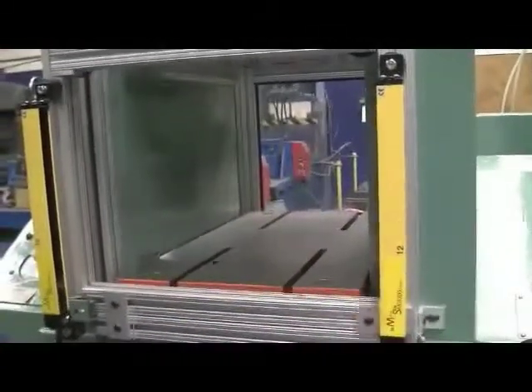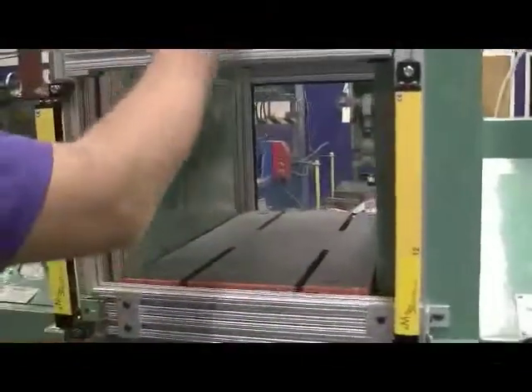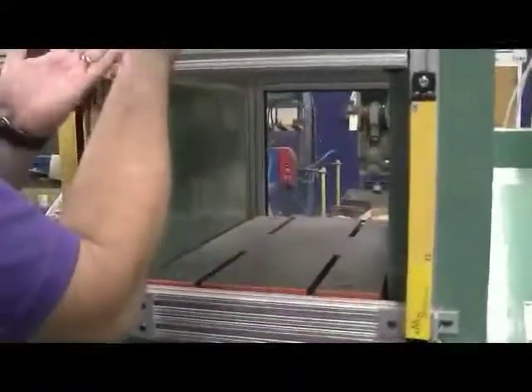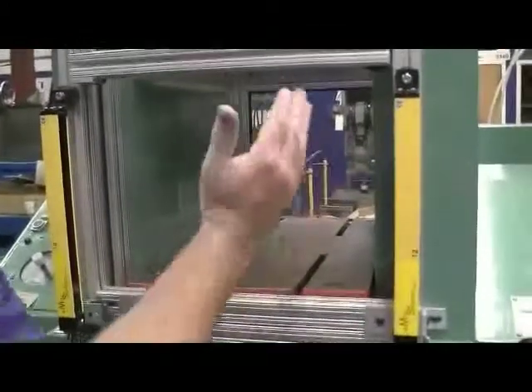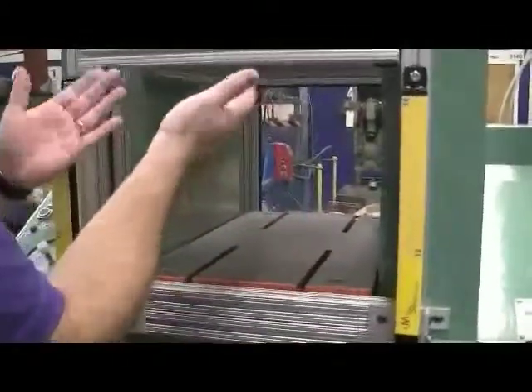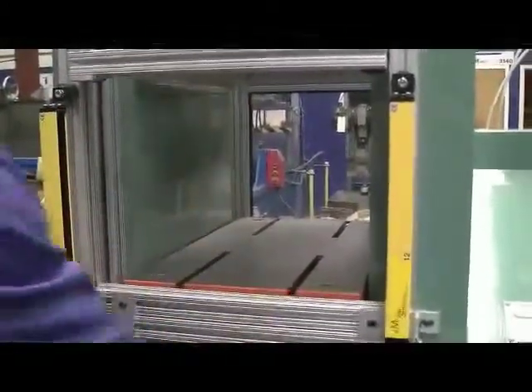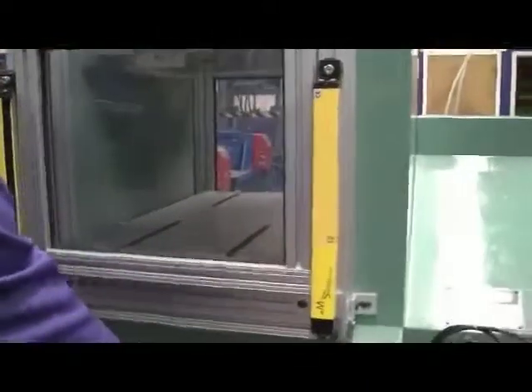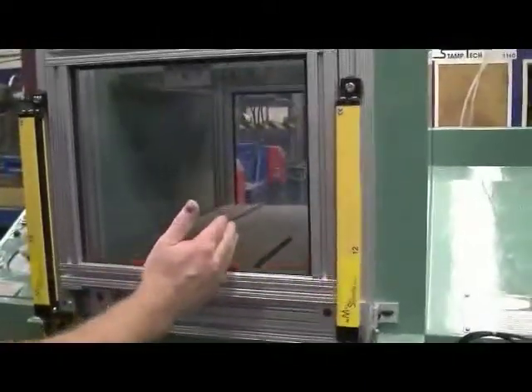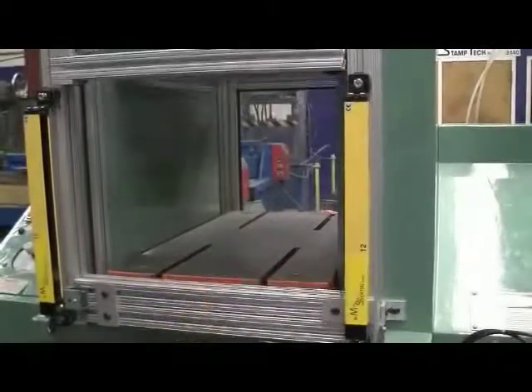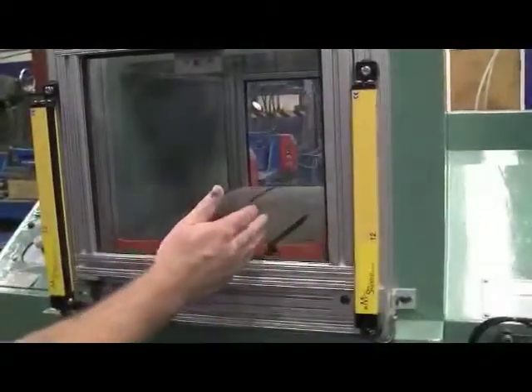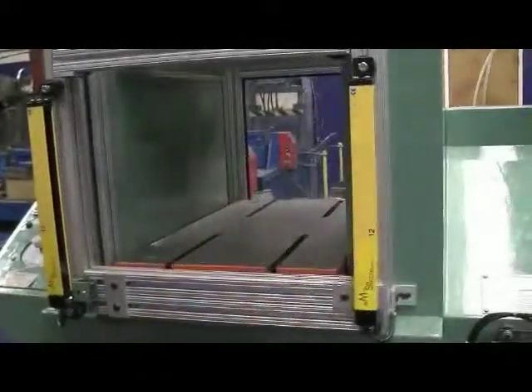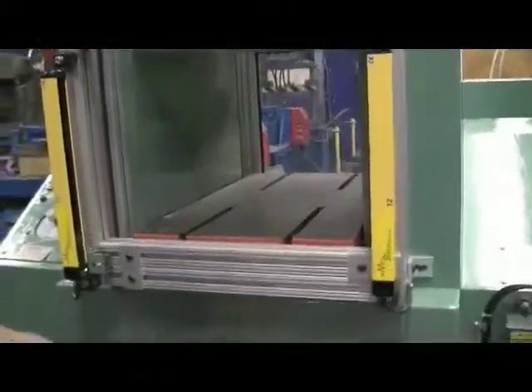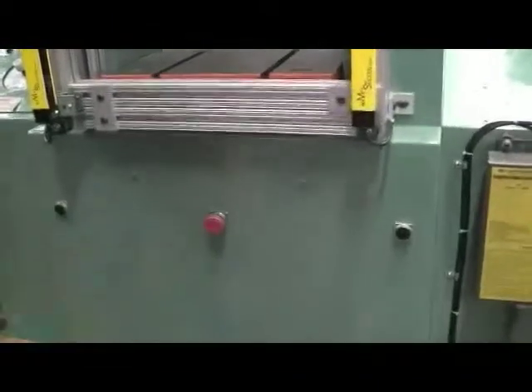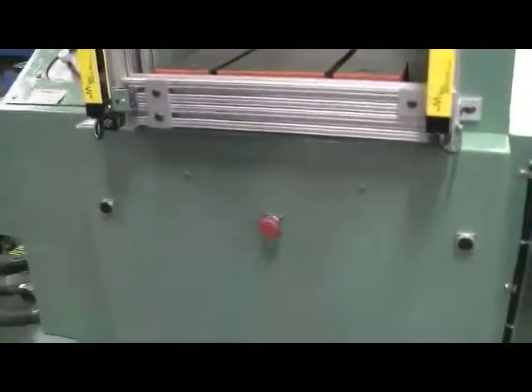The way the light curtain works, if you break the beam as the gate is coming down, the gate will reverse and go back up. Also, if you break the beam as the ram is going up, the ram will retract to its home position. Just like that. You have an emergency stop button over here, and as soon as it's depressed, the press stops cycling.